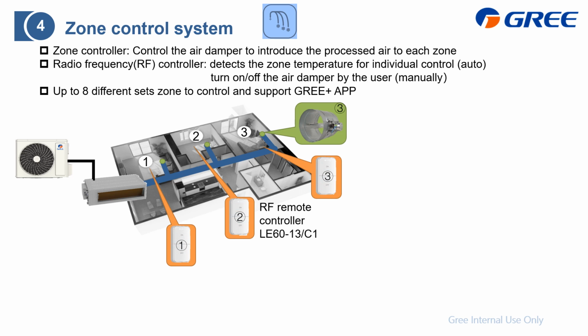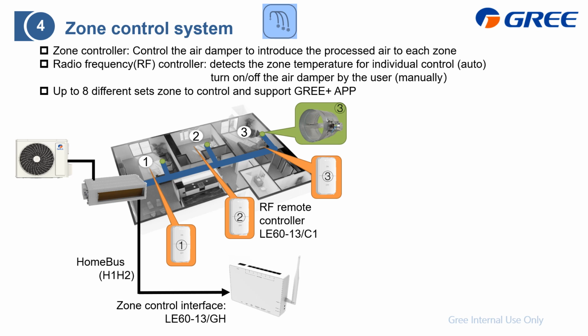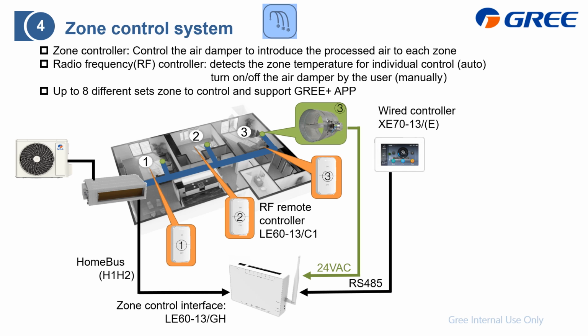And for this one, there is an additional RF, short for radio frequency, remote controller. With this one, it is wireless. And then this one is the zone controller device. You need to connect it to the duct type indoor unit. And then here is the air damper, which also needs to connect to this controller. The wire is 24 volt AC. And this is the control interface, this controller, and it also needs to connect to this one.